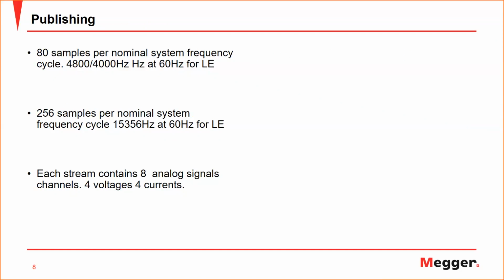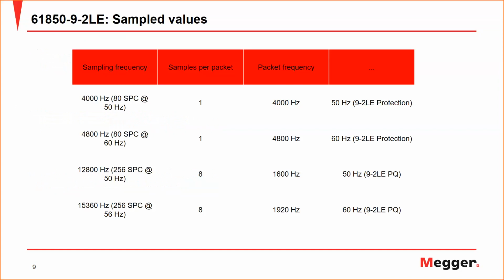This is mainly used for what we call the power quality metering requirement, since you require sub-cycle knowledge to assess transient behaviors. Mainly each stream of these published sampled value messages will contain 8 analog signals. It will be 4 voltages and 4 currents. These 4 voltages and 4 currents could be like 3-phase voltage and neutral voltage, 3-phase current and neutral current, or could be used only, for example, 3 currents in 2 different merging units, for example, for differential protection. So these are the sampling values defined by the light edition.